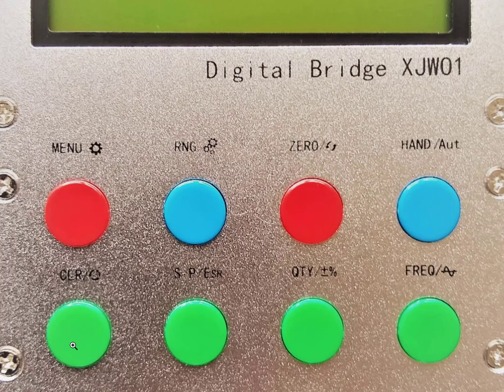Okay, next we come to this CLR button, which actually doesn't mean clear, it means capacitance, inductance and resistance. So this changes the mode from auto, which means fully automatic. It'll try and determine what the device under test is and set the best measurement, display the best measurement for you. If you press this button, you can cycle through auto C, auto L and auto R, and then back to auto again. So it'll keep it on either the capacitance measurement range, the inductance measurement range, or the resistance measurement range.